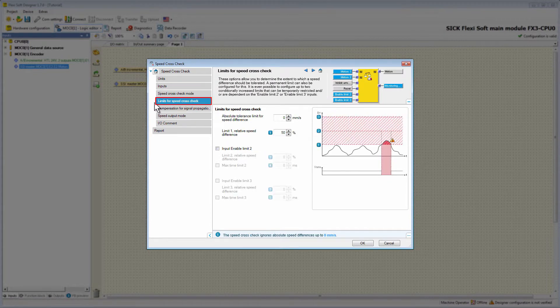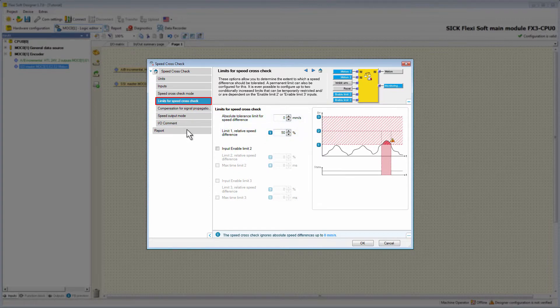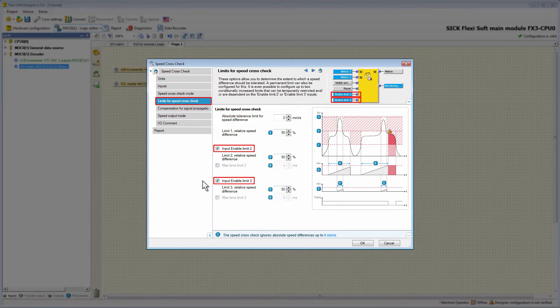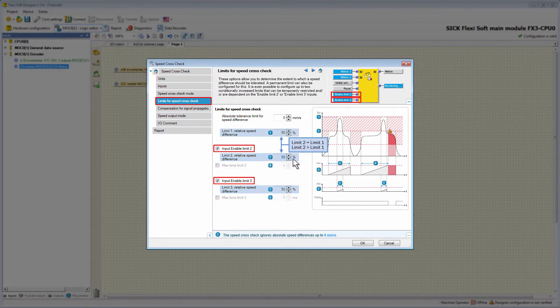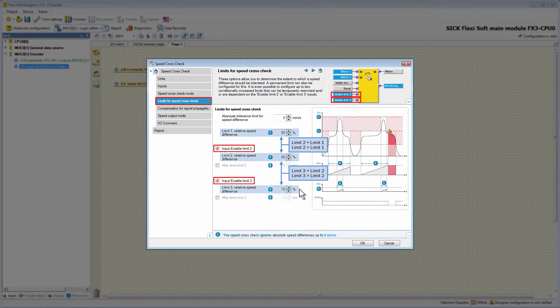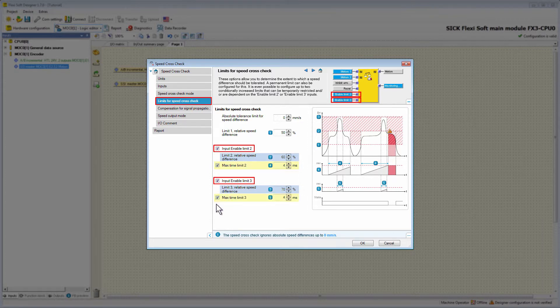In the tab Limits for Speed Crosscheck, it's possible to determine up to which level a speed difference is tolerated. The permanent limits — absolute tolerance limit for speed difference and Limit 1 relative speed difference — are set here. Furthermore, it's possible to enable two additional inputs, EnableLimit2 and EnableLimit3. If these inputs are used and a high signal is present, then exceeding the value of Limit 1 relative speed difference is allowed in the amount of the configured values for the relative speed difference. The relative speed difference of Limit 2 must always be equal to or greater than that of Limit 1, and the same applies for Limit 3 with respect to Limit 2. Additionally, for each optional limit there is the option max time Limit 2 and max time Limit 3, with which the limits can be temporarily restricted.